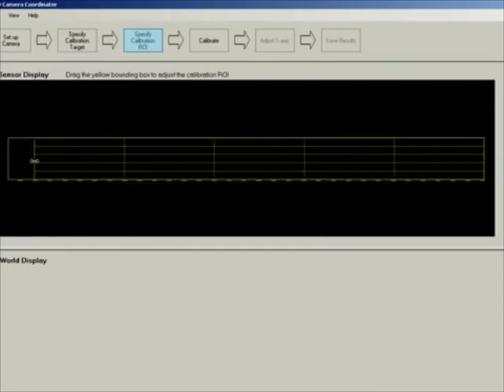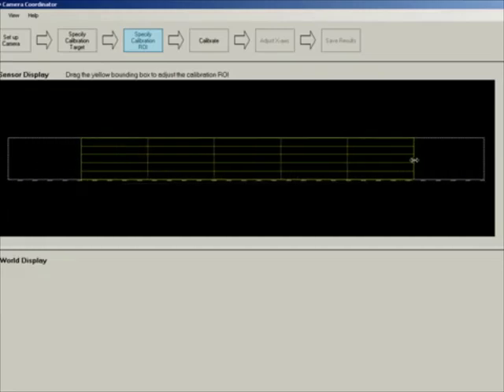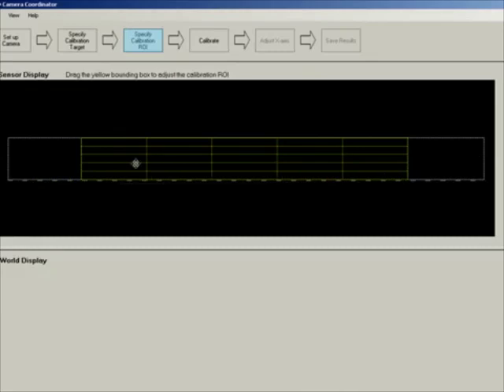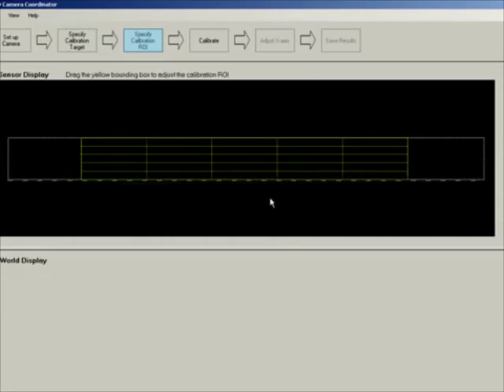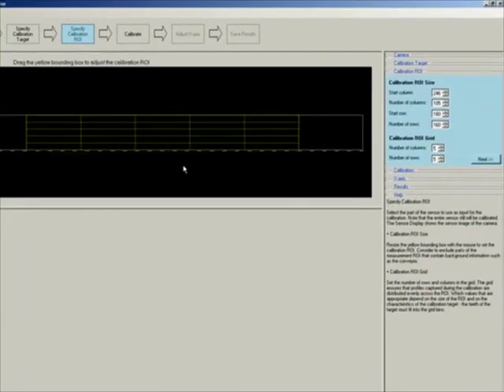You can cut down this region of interest, especially since many columns on the side may be on the conveyor and not on the part. What is shown in white represents the full region from the parameter file, and what is yellow is what I have chosen to calibrate. Note that calibration is extrapolated over the entire sensor imager regardless. I can also place the flat side of the calibration target at the bottom and make sure that area is included in my calibration ROI.